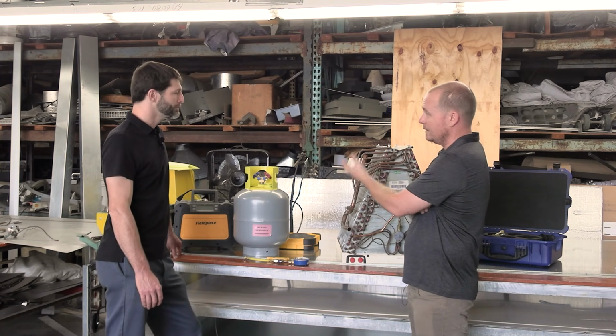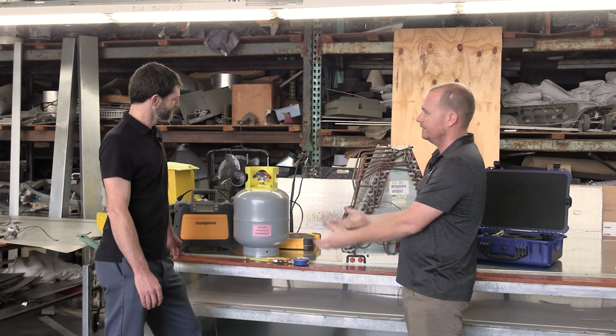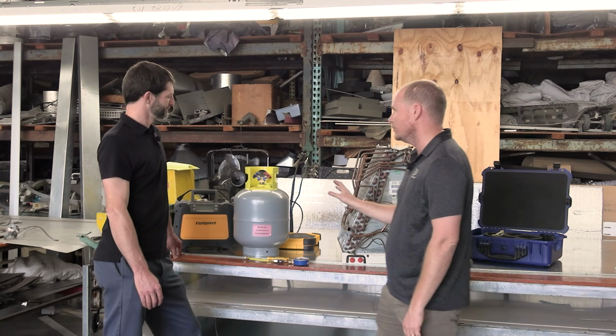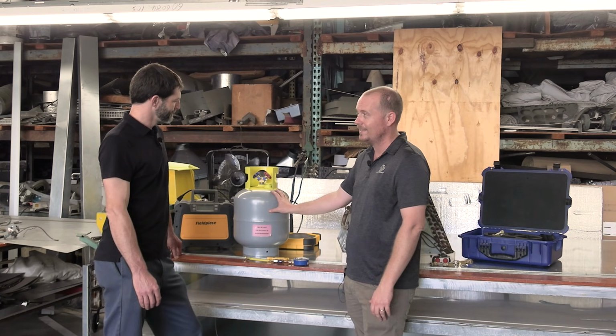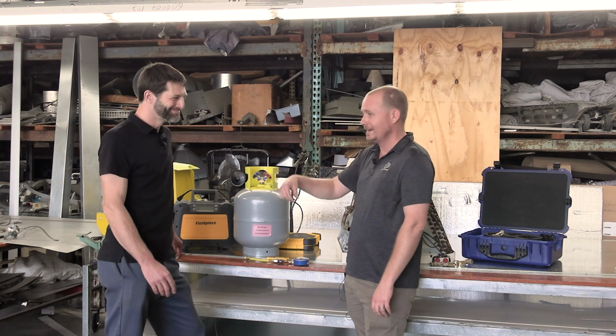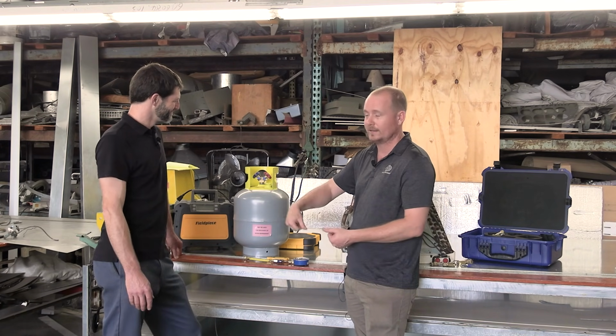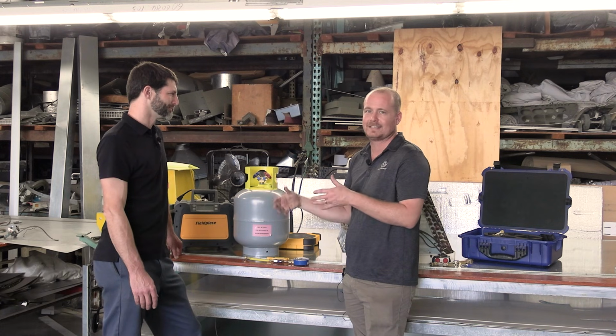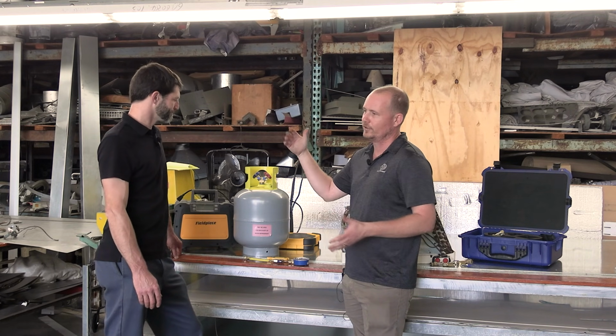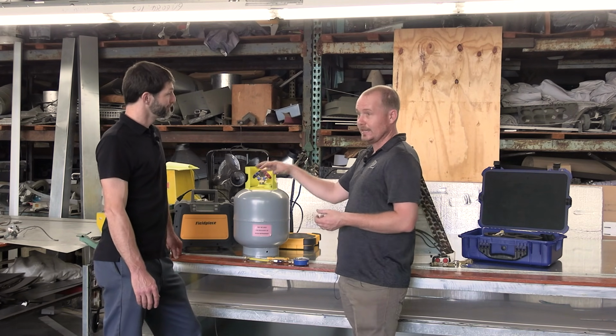Another thing in terms of keeping the tank cool, some people will put it in a bucket of ice, whatever, but keep in mind that when you're doing that, you still have to keep weighing it, and that gets really tricky when you're putting it into a bucket of ice. So you need to periodically pull it back out. Now, you can generally have a sense of whether or not you're overfilling. You know whether you're getting close or whatever, but you need to still keep weighing it.